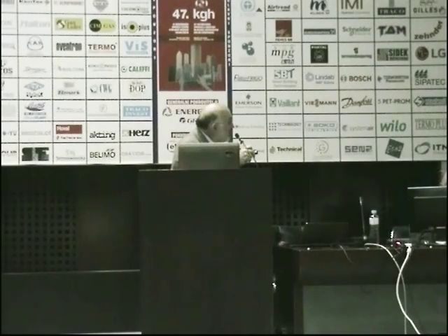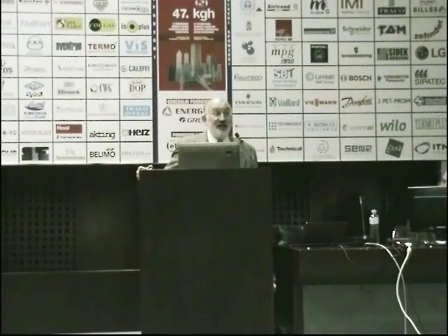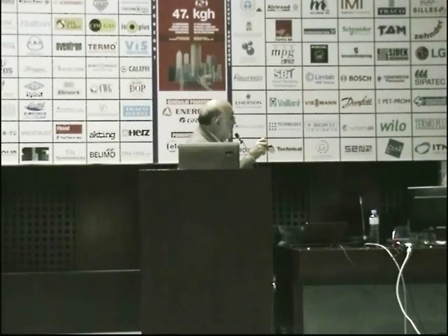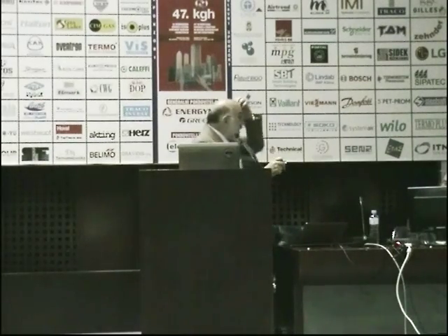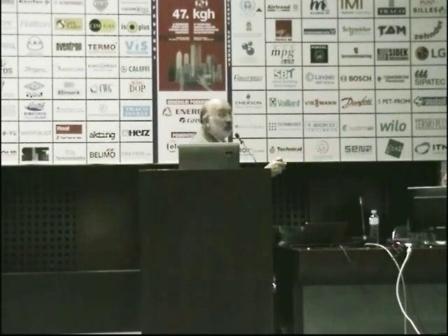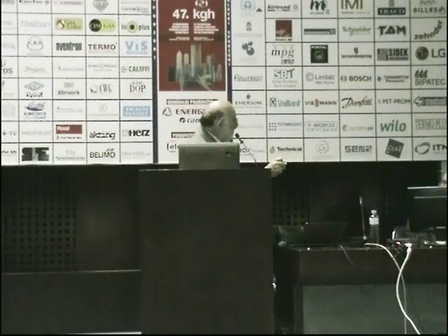Here what is interesting, I'm showing you for the same condition two fluids, 134A and 32, and I think we will have towards the end of the presentation something about 32, and you will see a little bit more data later. It is very interesting, and whoever has done any measurement with 32 knows it has extremely good heat transfer characteristics, much better than, for instance, 134A. And one of the reasons is that it has a much higher latent heat, and thus the film here is much thinner than for, let's say, 134A. Ammonia would have an even thinner film.